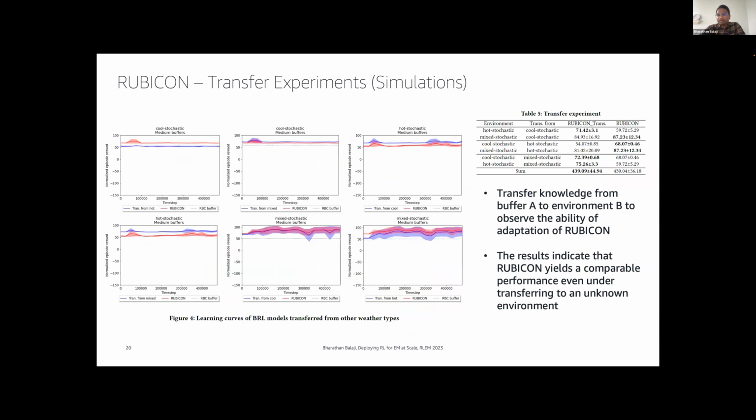So you might have spent a lot of time in an experimental building, and you have a reinforcement learning policy there with some historical data. And now you want to take those learnings and deploy in a real building, in a different building, which has its own rule-based policies. So now when you combine the best of both, that's a really good direction we can go to, because the rule-based policy learns a little bit from the reinforcement learning policy, and both get combined to get savings. And the numbers here indicate that if you had just not used the transfer and used the same building's historical data, it would have gotten you about the same amount of reward. So the transfer is actually quite effective here.